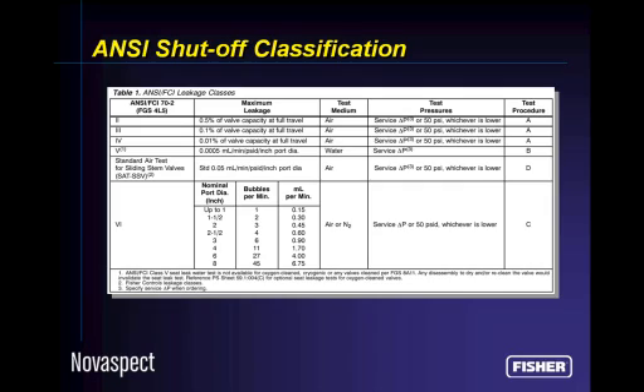So if it's good enough that it's a control valve and it doesn't really need to shut off, call it an ANSI Class 2 valve, and only pick tight shutoff when you absolutely need it. We prefer that you use a motor-operated gate valve or manually operated gate valve or something like that if you really need tight shutoff during long periods of time.